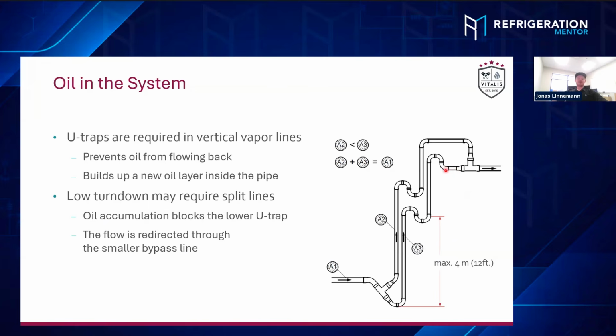And it's also important to have at the very end, either when you connect to a gas cooler on top of the building or in suction lines, same thing, to have a little U-bend at the top to prevent, when the system stops or when it ramps down, that the oil flows back the whole way, right? That would be very bad.